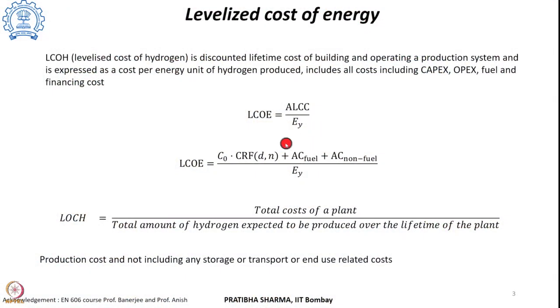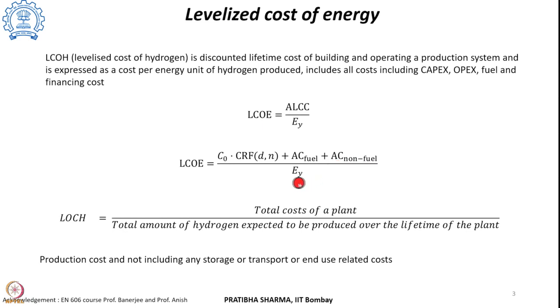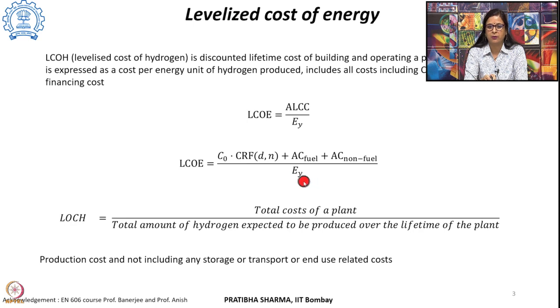We can also find the levelized cost of energy by dividing the annual life cycle cost by the amount of energy that plant produces over its lifetime. The life cycle levelized cost of energy is the initial investment times the capital recovery factor plus fuel-related and non-fuel-related operation and maintenance expenses, divided by the total energy produced during the life cycle of the plant.